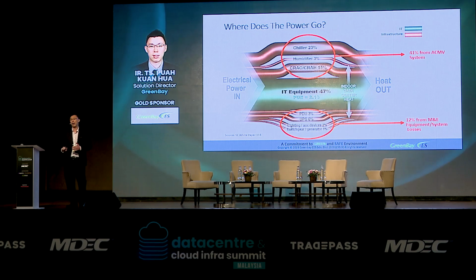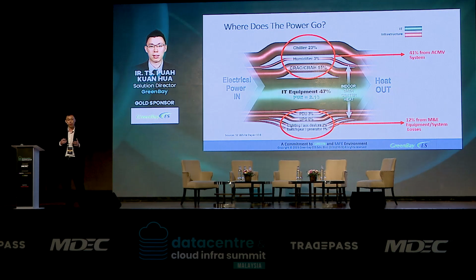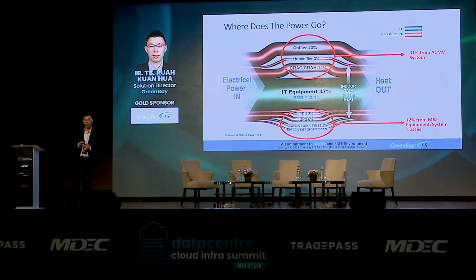This is a very good illustration for you all to understand where the power goes. For a typical data center with PUE of, for example, 2.13, where does the power go? You can see 47% goes to the IT equipment. The thing we need to improve for the PUE is mainly contributed by the ACMV system, which contributes about 41% of the overall.